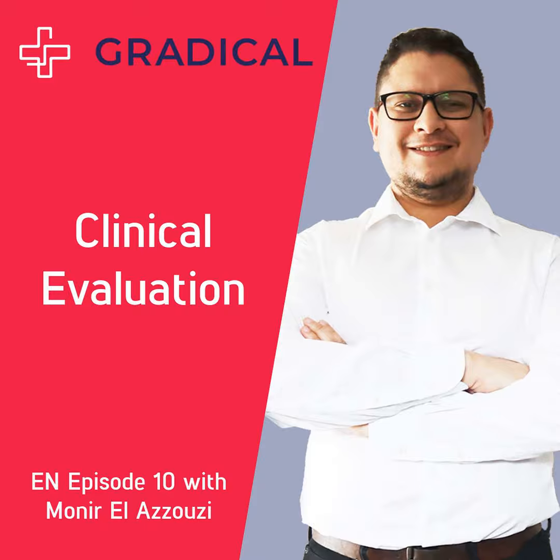Yeah. So I'm really interested to know. I do this whole clinical evaluation, find my state of the art, and then I try to find clinical data for my device. First of all, if I do a clinical investigation, so I do clinical testing on patients, am I obliged to publish this? Normally, yes. I saw some that stopped the clinical investigation. So as they haven't finished it, they haven't published anything. But if you have done the clinical investigation, yes, you have to publish.